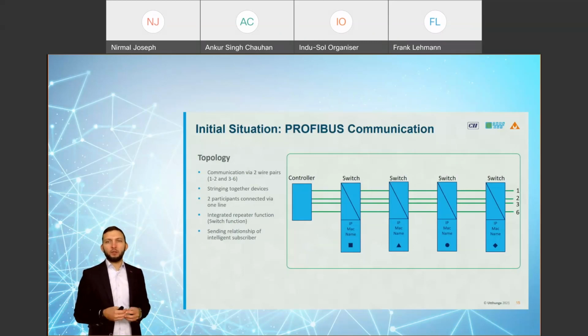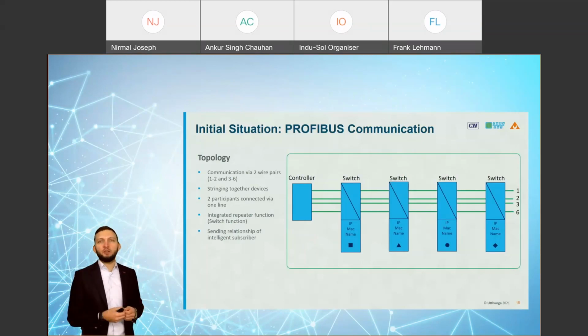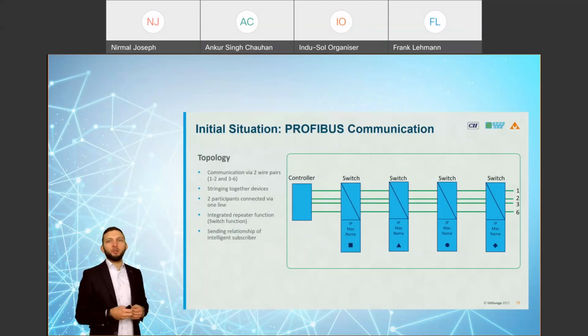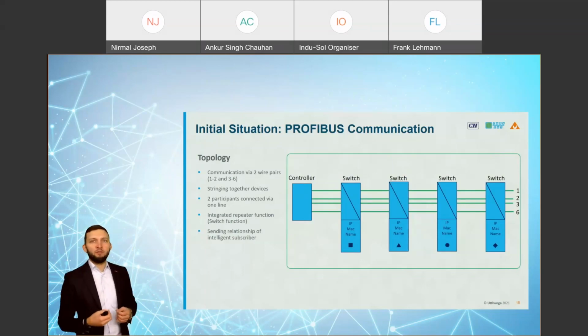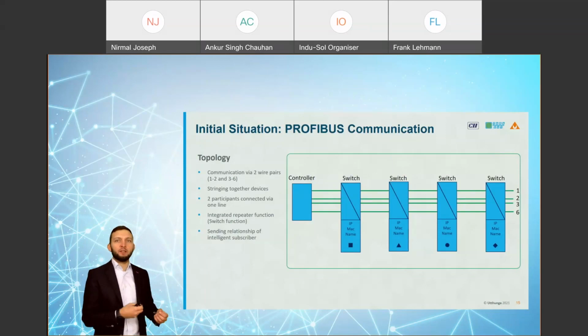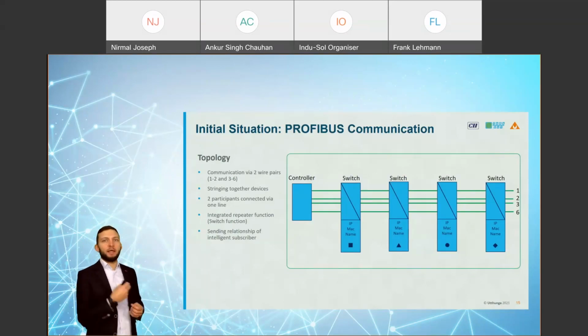Going deeper, we want to see what the biggest benefit is if there's a line error and so on. Another case is that I don't have master-slave communication in my PROFINET network; instead I have real-time communication based on update times. That means the controller has to send information to the device at its own update time, maybe 1 or 2 milliseconds, and at the same time the device also has to send information back to the PLC within the same update time. It's not a request and response, it's only sending information.